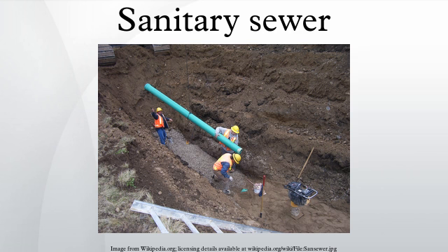A lift station is a gravity sewer sump with a pump to lift accumulated sewage to a higher elevation. The pump may discharge to another gravity sewer at that location or may discharge through a pressurized force main to some distant location. Maintenance. All sewers deteriorate with age, but infiltration and inflow is a problem unique to sanitary sewers, since both combined sewers and storm drains are sized to carry these contributions.